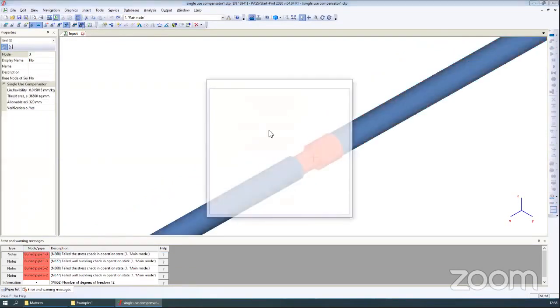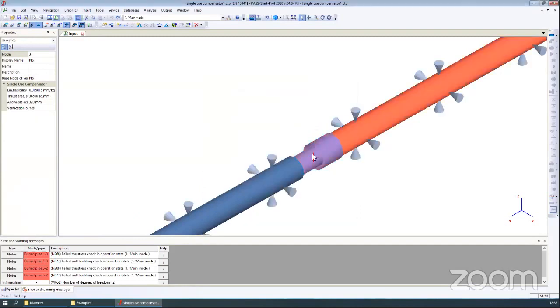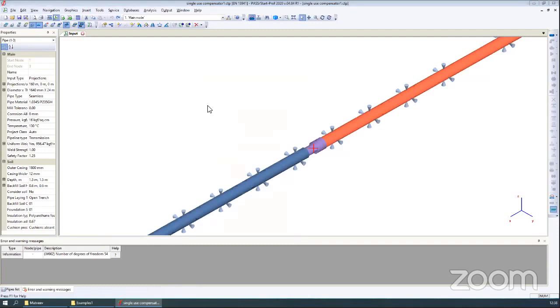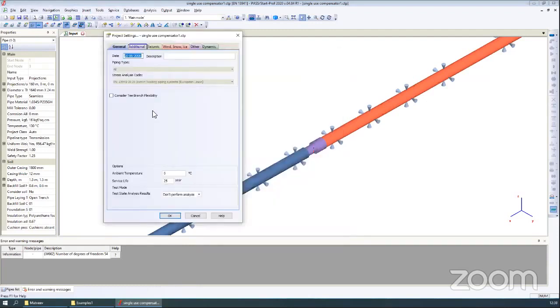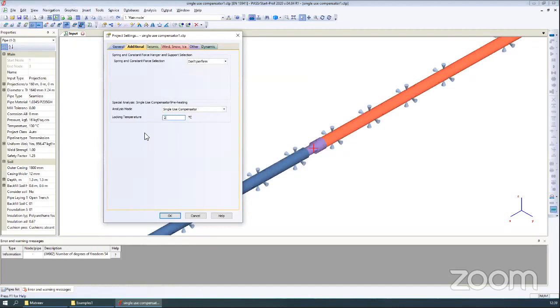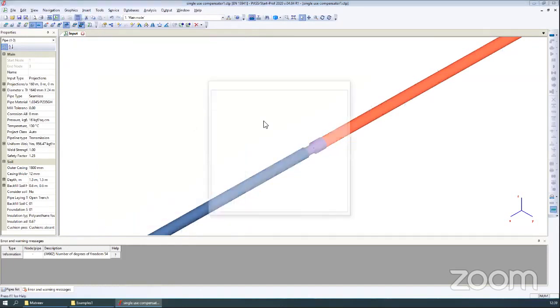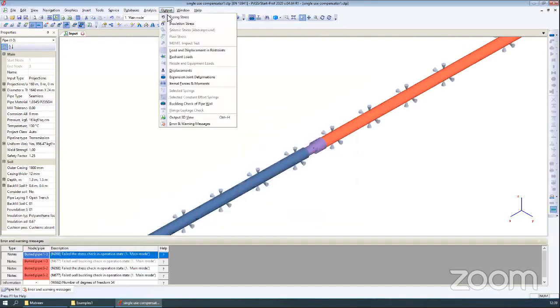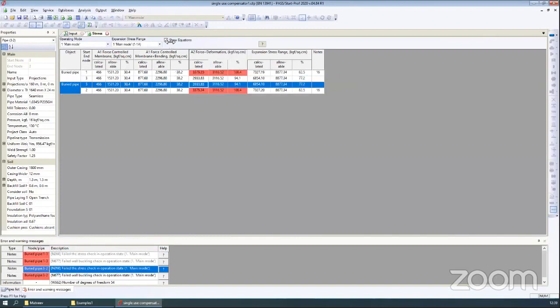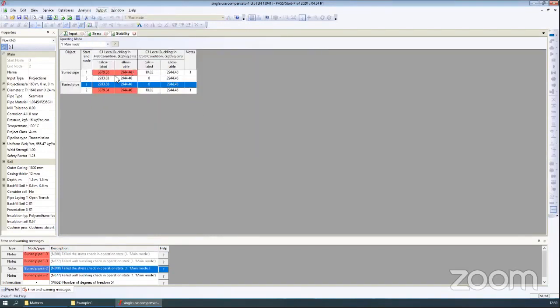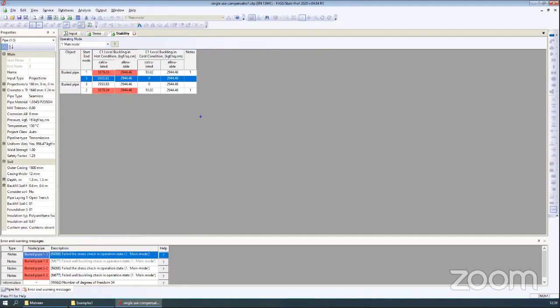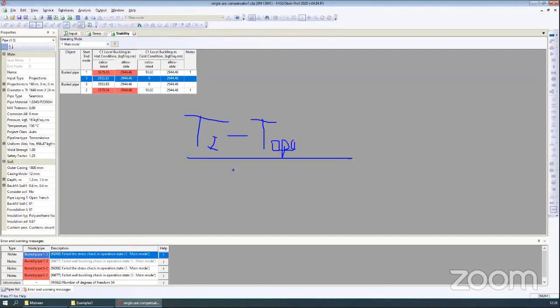Now I remove the single-use compensator from this model and run the analysis again without it. You can see that we have problems with the stresses, and we also have a problem with buckling. So the single-use compensator helps us a lot. I undo the changes to return the single-use compensator, and then change the locking temperature from 65 degrees to 20 degrees. Running the analysis again, you can see we also have some problems with stresses. So the locking temperature should be the temperature between the installation temperature and operation temperature divided by two — that is the correct locking temperature for single-use compensators.